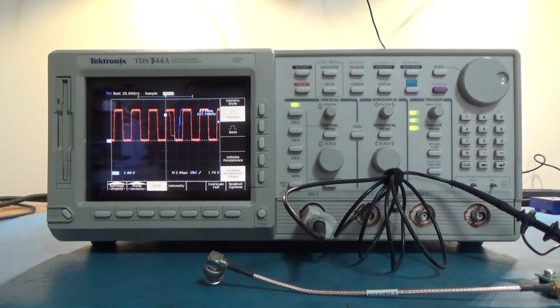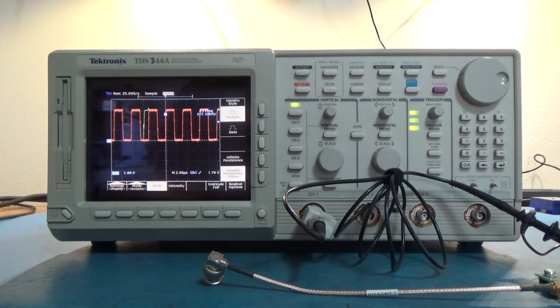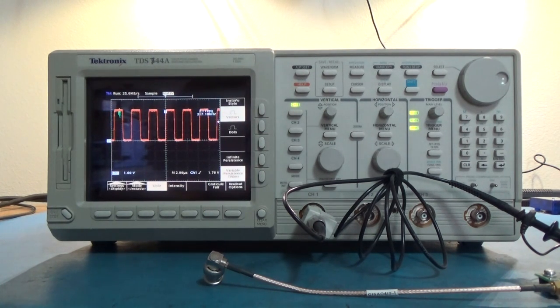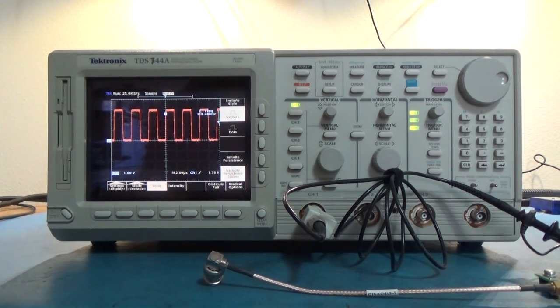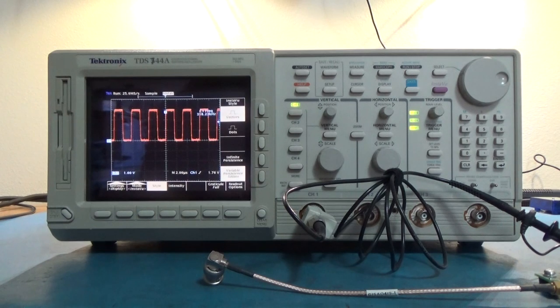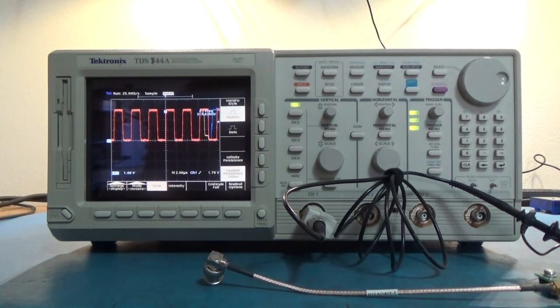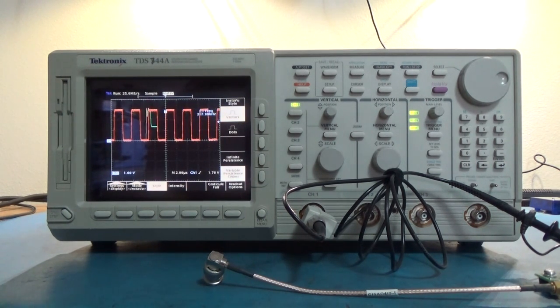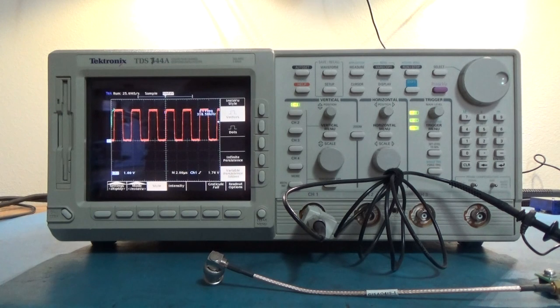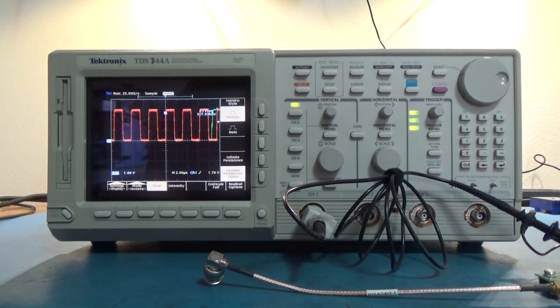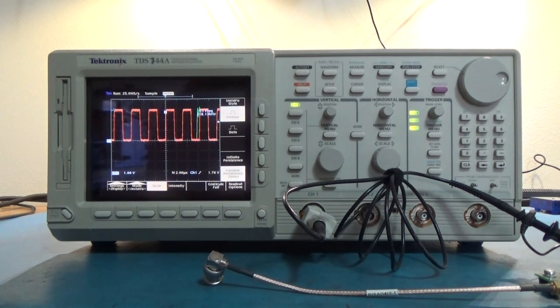But when the 700As came out and the 500Bs came out, they were a new design. They'd done away with the capacitors, the electrolytics completely on the acquisition board. With the early scopes and the capacitor problem, it was leaking electrolytics. Some things were shorting. Data lines were getting burnt out. And it's unpredictable.